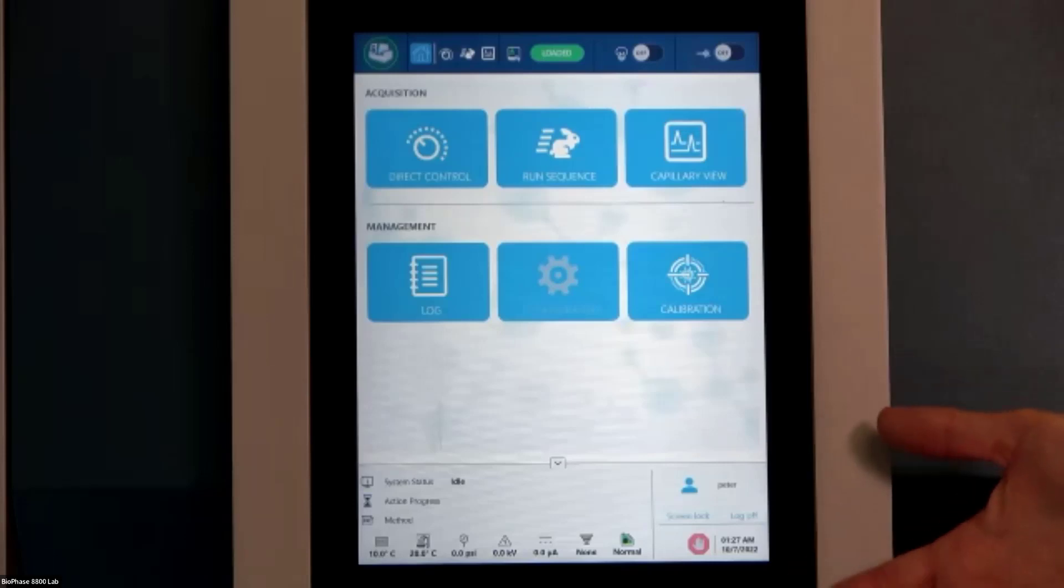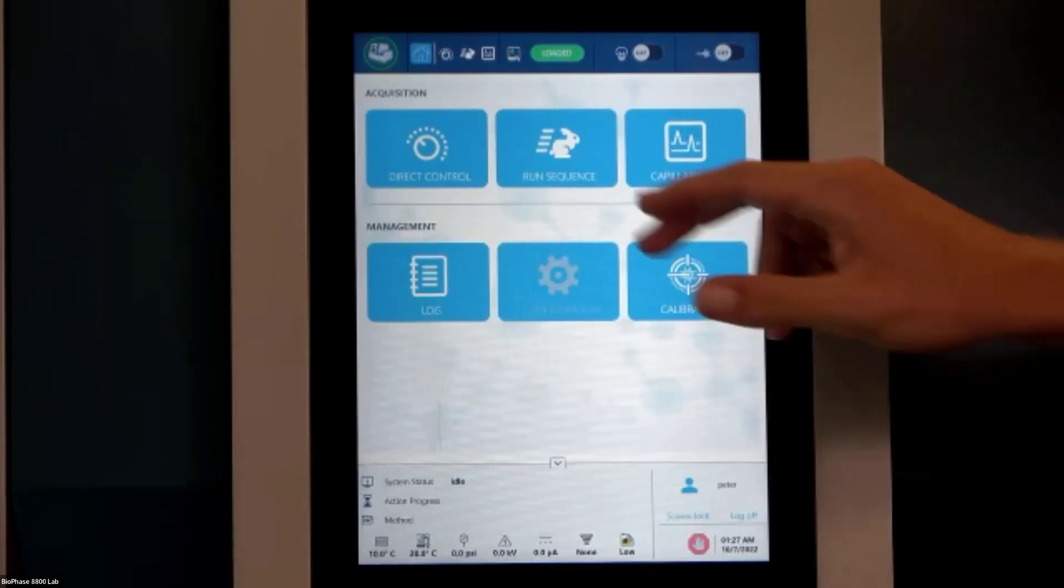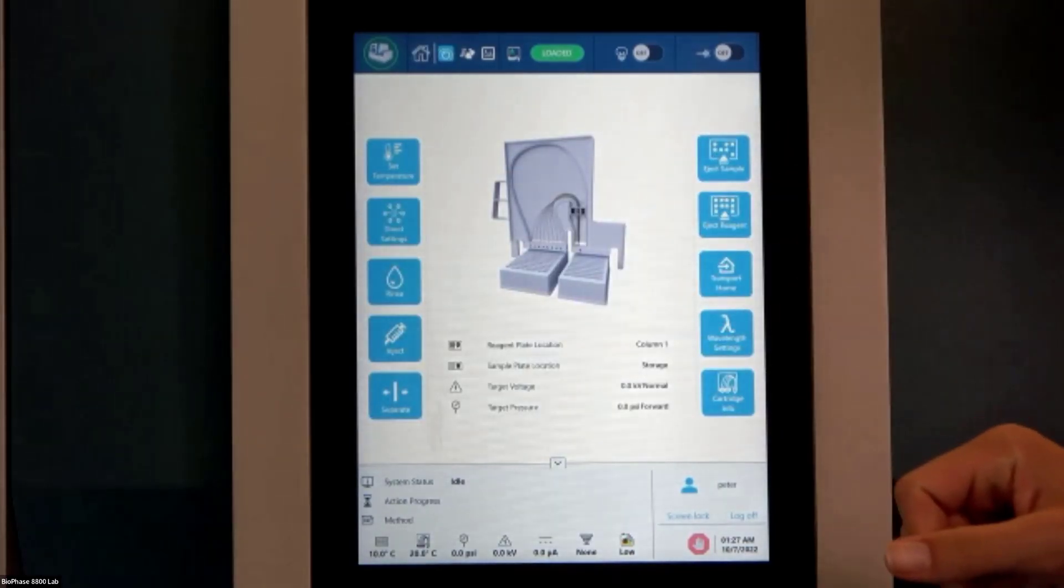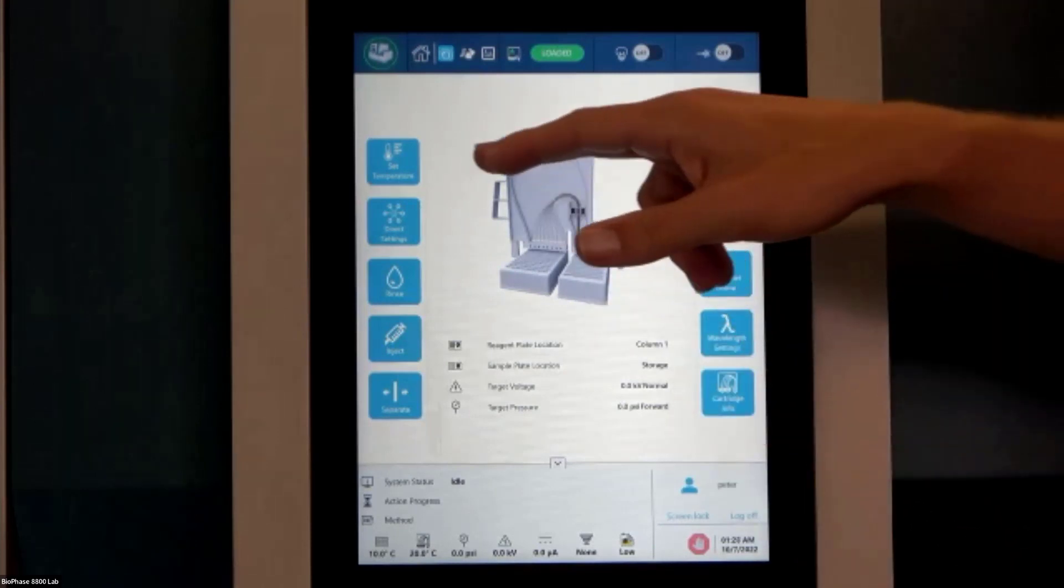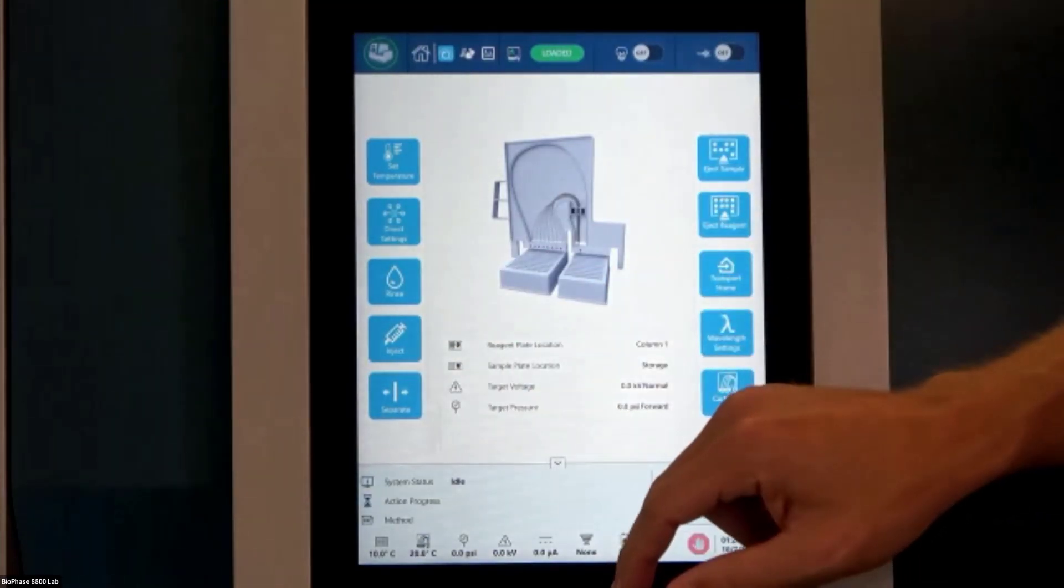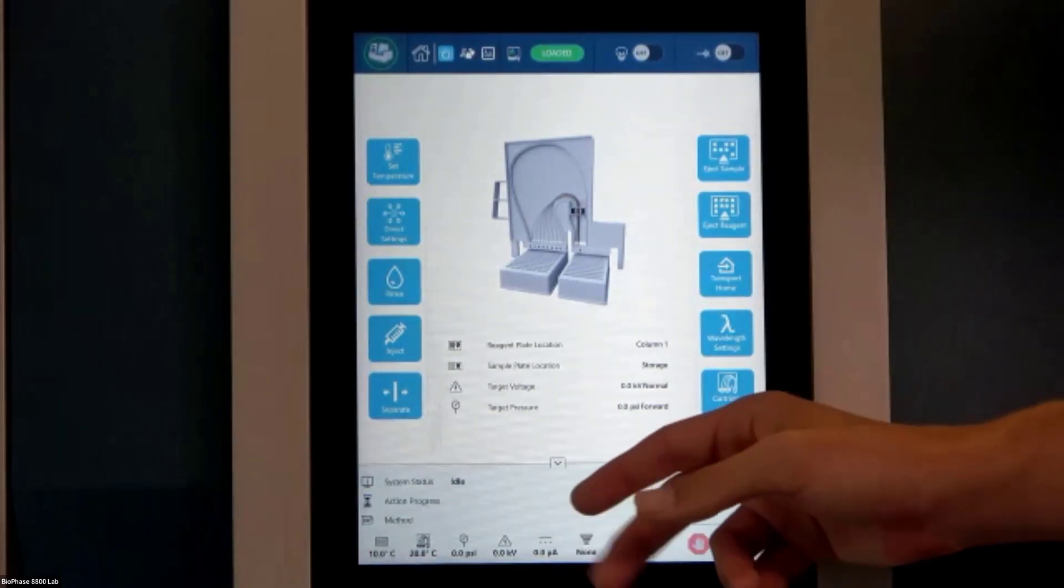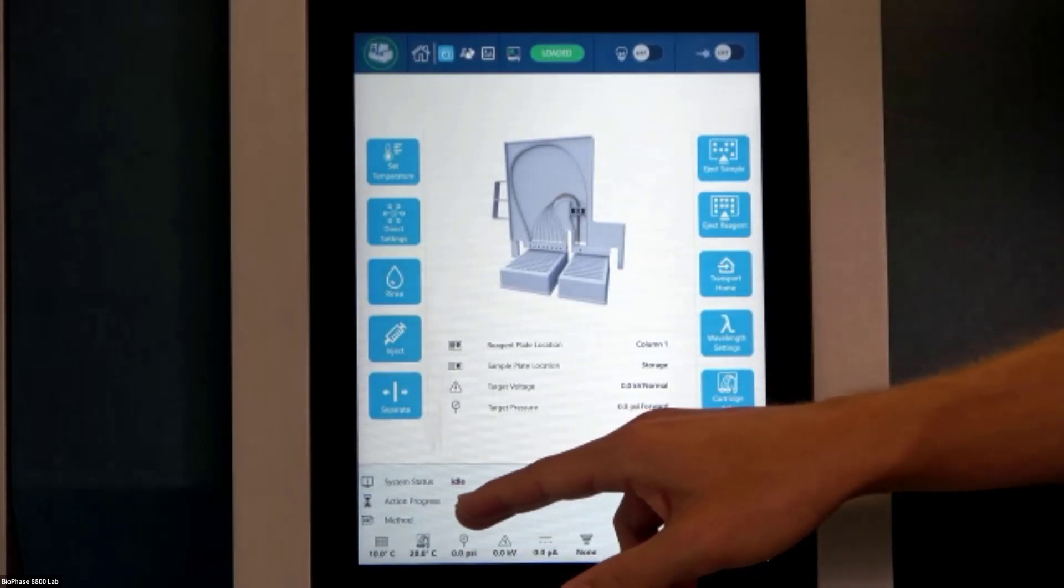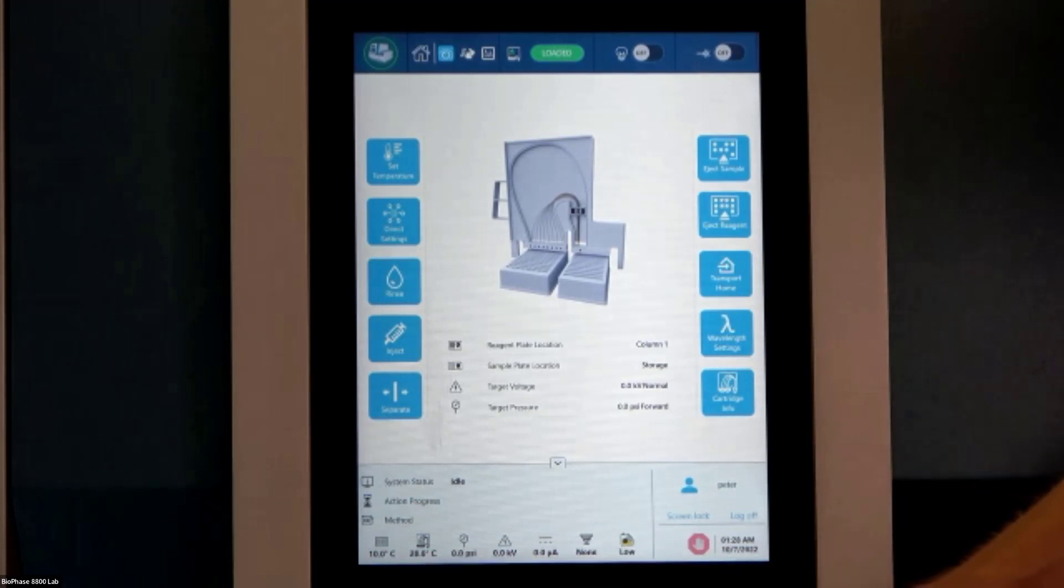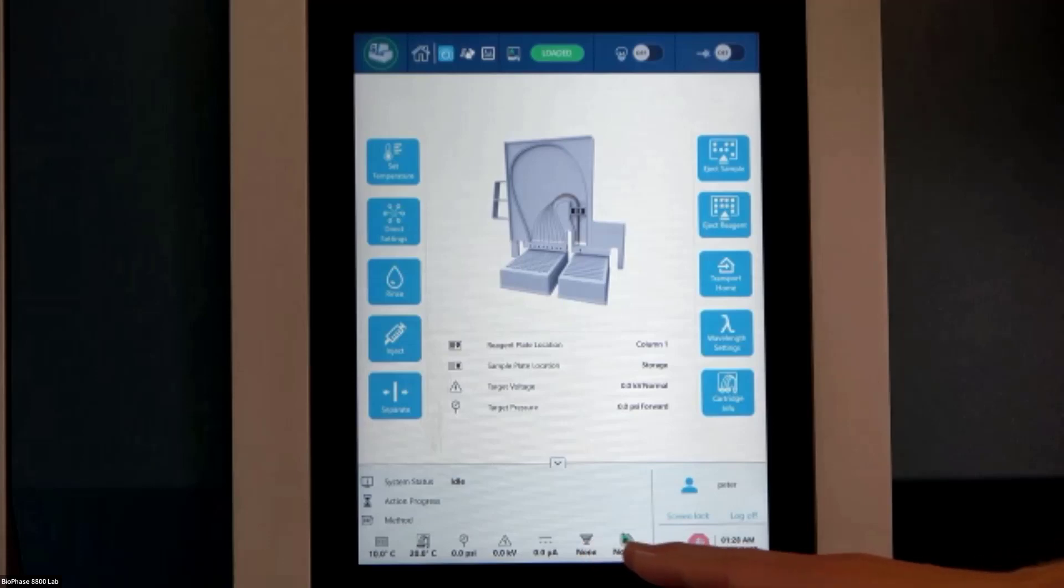So here we are, our front panel. This is really nice. It's a touch screen interface with a lot of these different icons here. The first one that we have is our direct control icon. For users of 32 Karat or Empower Control in their PA 800 Plus, they're going to be familiar with a lot of this stuff. We have icons here to manually set our cartridge or sample storage temperature. We can do manual rinses, manual injections, manual separations. When our system is running, down here it's going to display exactly what's going on. Our system status, what is it doing? Is it rinsing? Is it separating? How long has that action progressed for? One minute out of, say, three minutes? What method we're running? Sample storage temperature? Cartridge temperature? Applied pressure currently? Applied voltage? Generated current? What detector, the UV or the laser are we using? And how does our coolant level look?